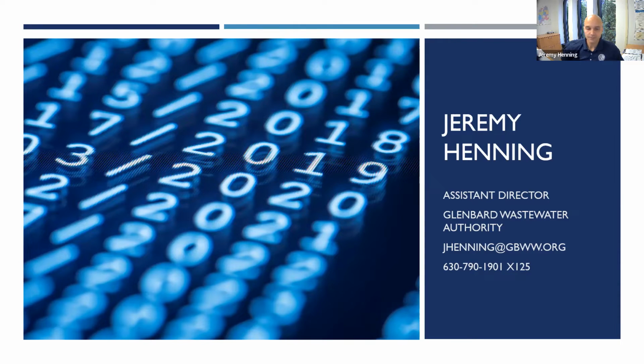Just because, no offense to manufacturers, they say this is what the set point should be - well, prove it to me. Let us make sure. We still have some gap there. As part of the UVT we ran it at 19 and knew we were still getting the throughput we needed and still disinfecting appropriately. So hold their feet to the fire, or come up with opportunities to find this information out for yourselves. Don't necessarily just trust that because that's always how it's done, or because the manufacturer says it should be done that way, that's how we have to run it. Things tend to be a little more unique in everybody's different scenario.